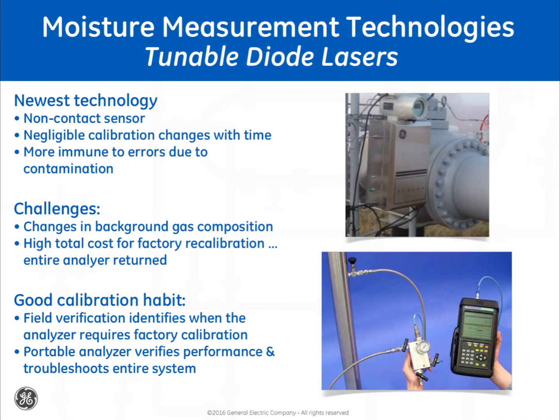Tunable diode lasers are the newest technology introduced to measure moisture. This technology offers an analyzer that exhibits negligible change in calibration with time. These are immune to measurement errors due to most forms of contamination. This is not to say that the electronics that drive these analyzers can't be in fault. Changes in background gas can also impact the moisture reading if the background gas compensation algorithm is not sufficient.